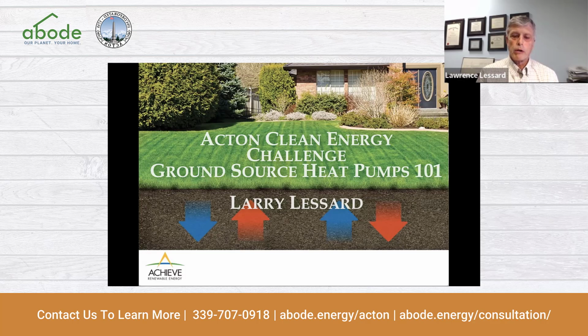So the particular proposal Mike was just talking about, the heating load for the house was at a certain level. We came up with a strategy to appropriately lower the heating load with verification that that was happening, and then did a system design for the improved house. That's a typical scenario for how we try to do our work, because ground source heat pump installations aren't cheap. If you can do some air sealing, insulation, other weatherization, and have us put in a system that reflects an improved building, then that's going to be a more economical install. And as Mike said, it's also going to have lower operating costs.